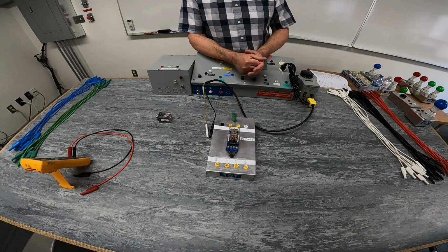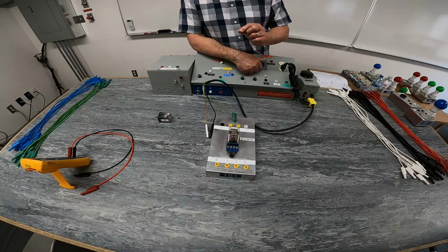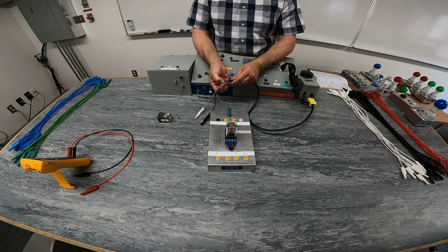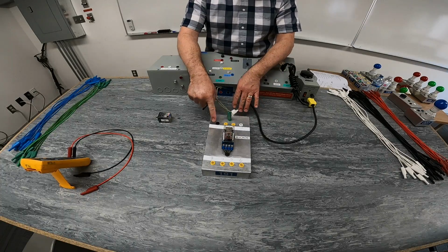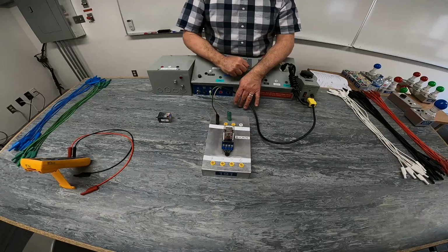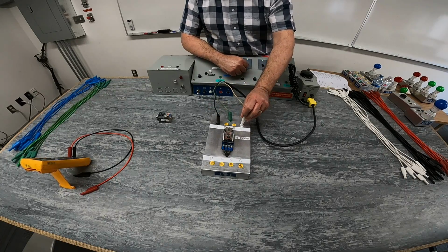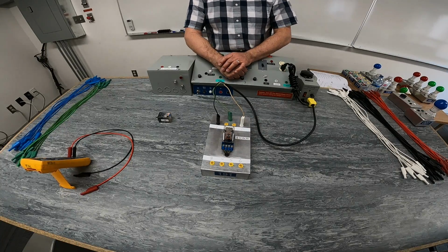So if you look on your coil, the termination points for my coil are points 2 and 7. So I'm going to take my line voltage, connected to, I've got some of my leads here labeled, termination number 2, and I'm going to put my identified over to termination number 7.